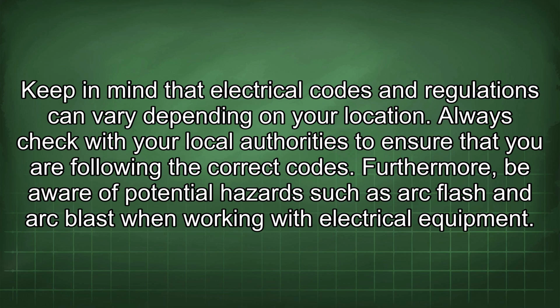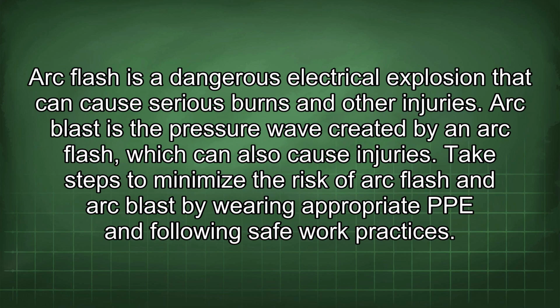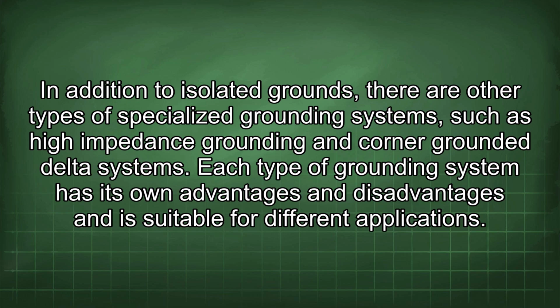Furthermore, be aware of potential hazards such as arc flash and arc blast when working with electrical equipment. Arc flash is a dangerous electrical explosion that can cause serious burns and other injuries. Arc blast is the pressure wave created by an arc flash, which can also cause injuries. Take steps to minimize the risk of arc flash and arc blast by wearing appropriate PPE and following safe work practices. In addition to isolated grounds, there are other types of specialized grounding systems, such as high-impedance grounding and corner-grounded delta systems. Each type of grounding system has its own advantages and disadvantages and is suitable for different applications.